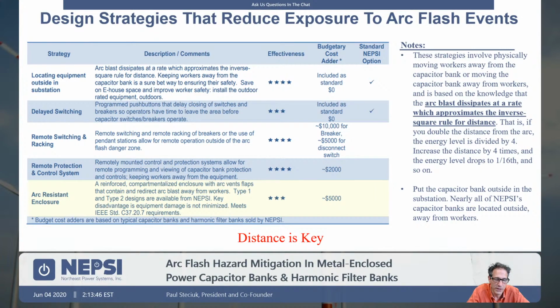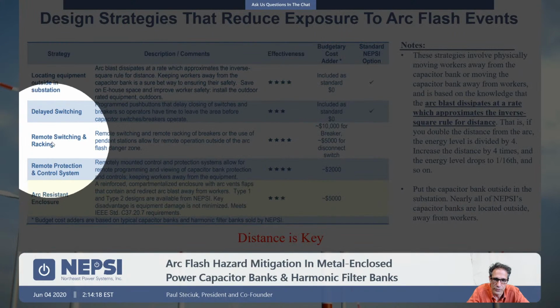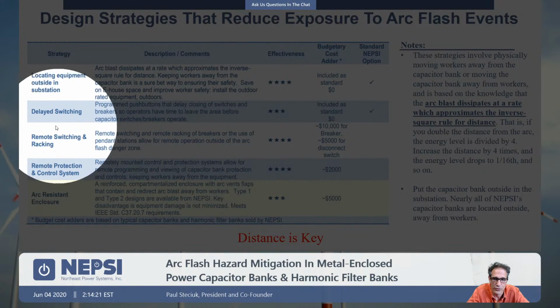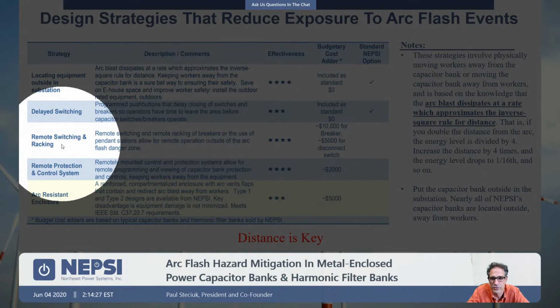When a capacitor bank switches, there's a lot of complex things going on. We're conducting current through the system. The vacuum switch is closing. We've had discussions about the complexity of capacitor bank switching transients. If the capacitor switch fails to do its job, you may have a pre-strike or a restrike condition that can result in case rupture, and can result in an arc flash event inside the enclosure. So why not step away? That's our recommendation, step away. If you have breakers within the gear, you can think about remote switching operations. If at all possible, consider remote switching. Do not stand next to the gear when you're energizing or when you're removing or racking out equipment.